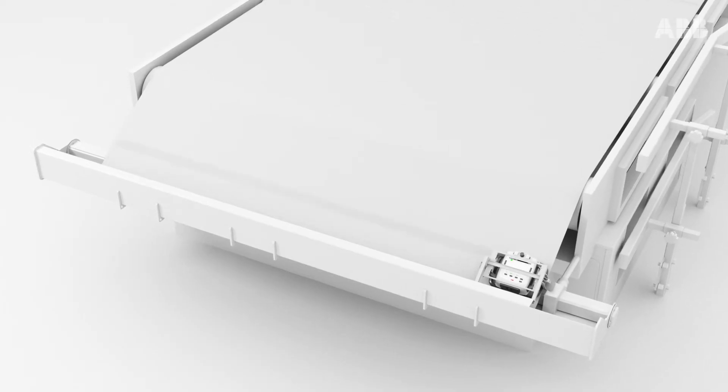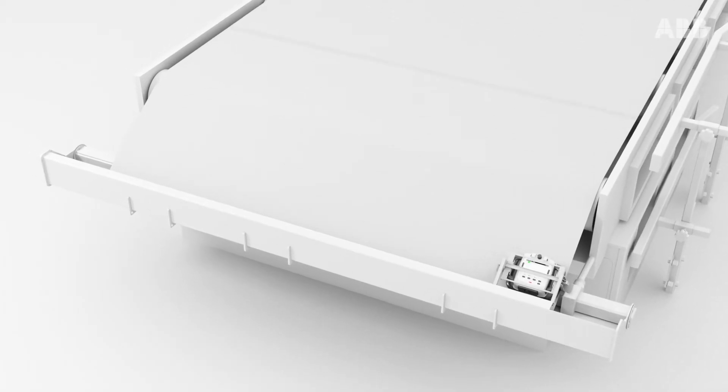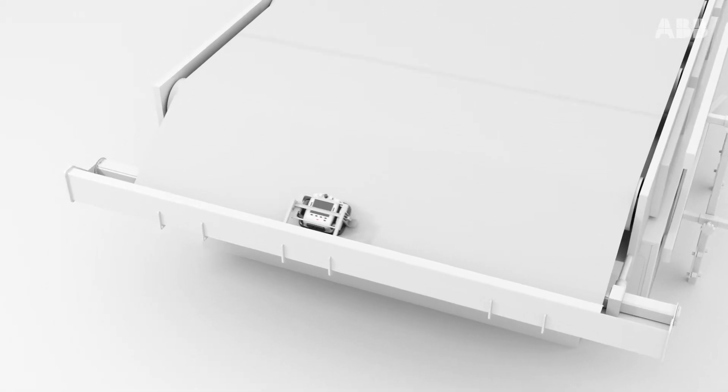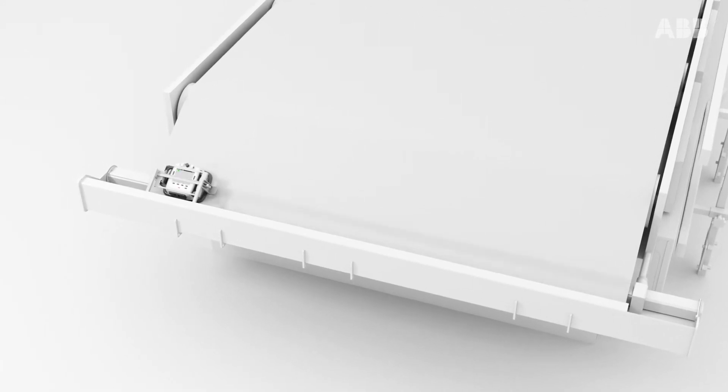ABB's units measure in both machine and cross-direction. For a CD profile, the shuttle moves across the moving felt collecting edge-to-edge data at a constant speed.